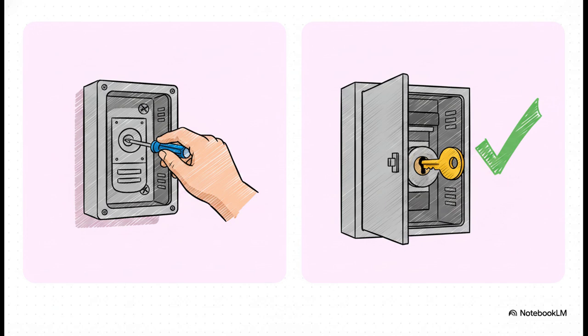The code makes a super important distinction between something being just accessible versus readily accessible. If a piece of equipment is only accessible, you might need a tool, like a screwdriver, to pop off a junction box cover. But readily accessible means you can get to it fast, no moving obstacles, no dragging out portable ladders, and definitely no tools. But here's the kicker, a crucial clarification: a key is not considered a tool in this specific context. So those circuit breakers locked safely inside a panel board still perfectly meet the definition of readily accessible.